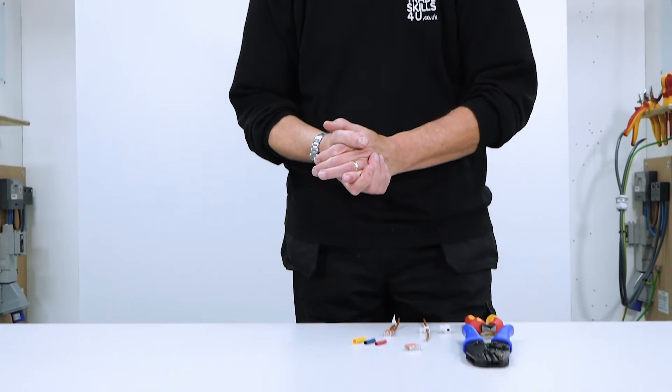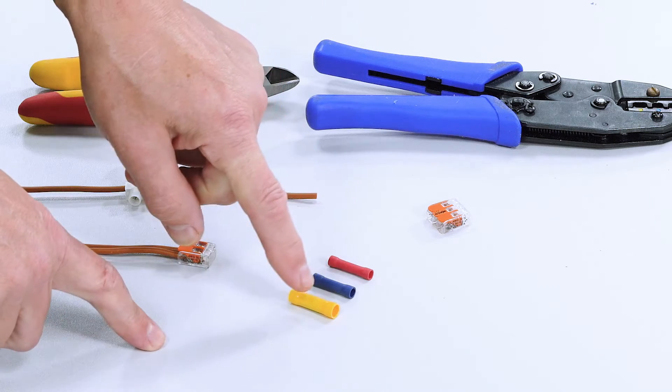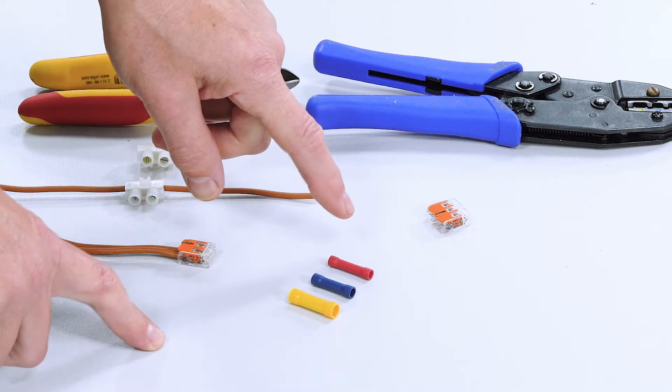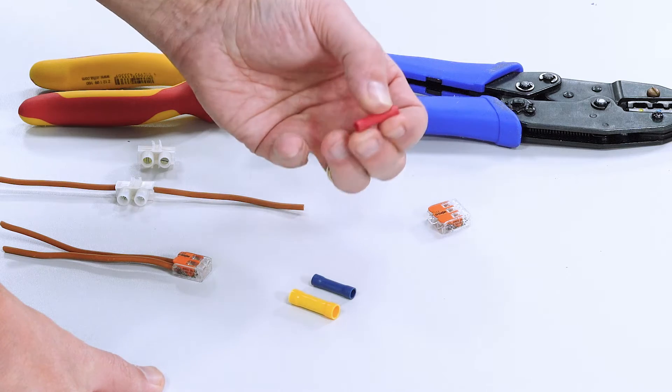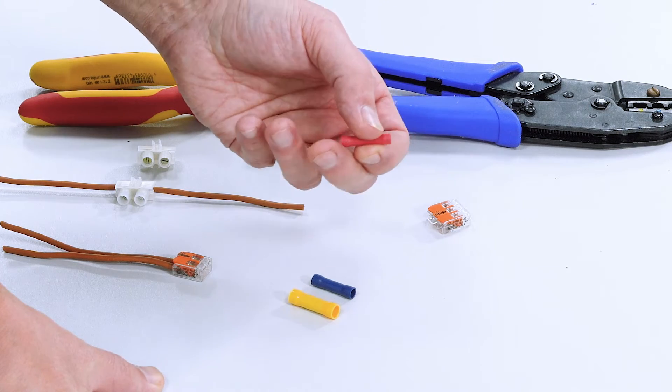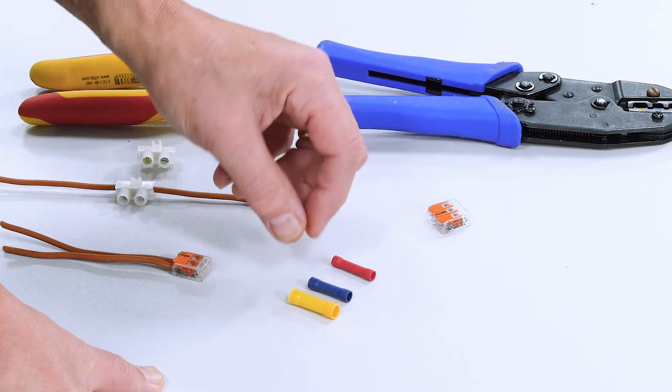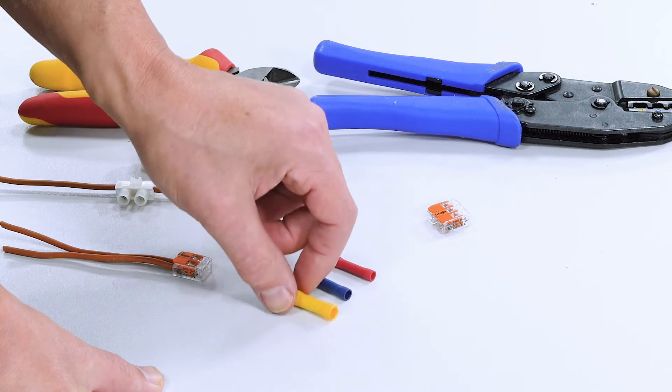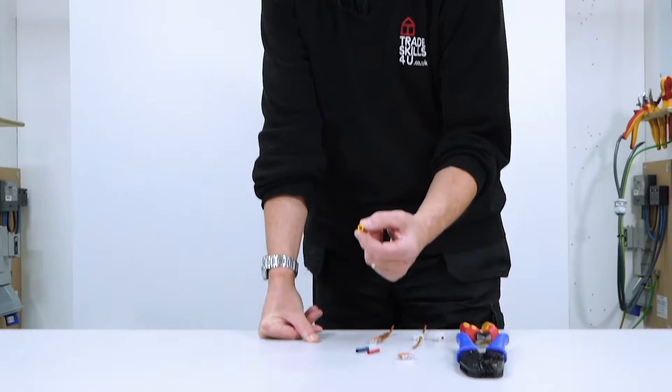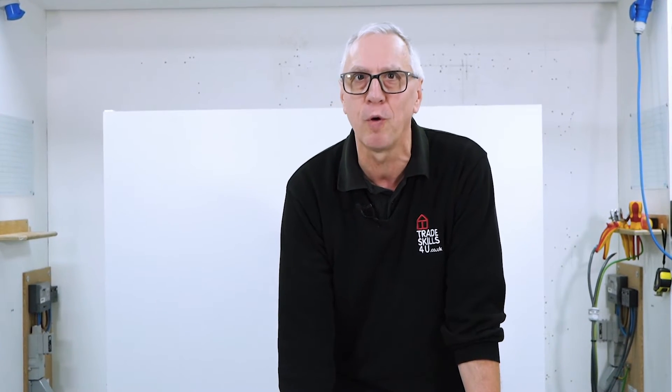And the method I'm going to show you today is by using these inline crimps. Now you'll notice we've got three colors here. The red crimp is for cable sizes of 1 and 1.5 millimeters squared. The blue is for 2.5 millimeters squared. And the yellow is for 4 and 6 millimeters squared cable. Today I'm going to be using the blue one for 2.5.